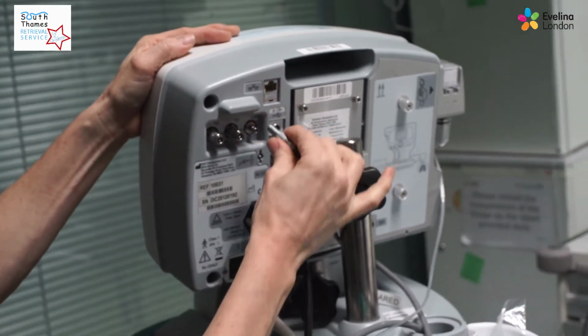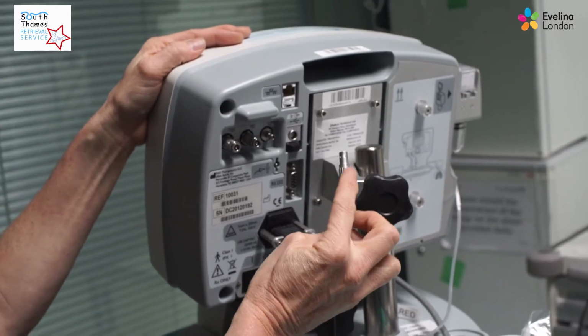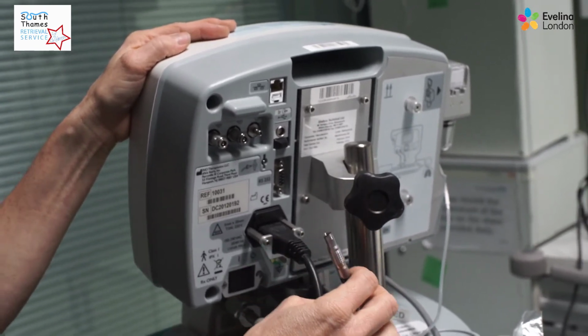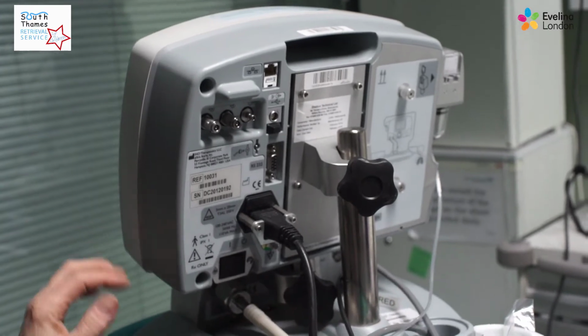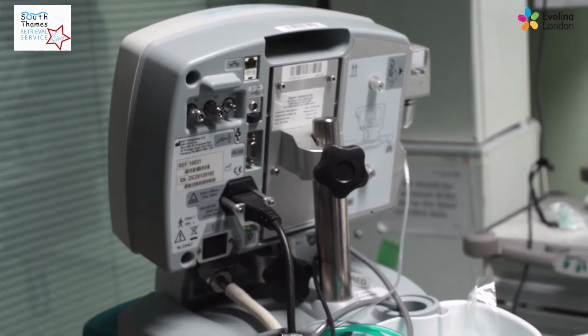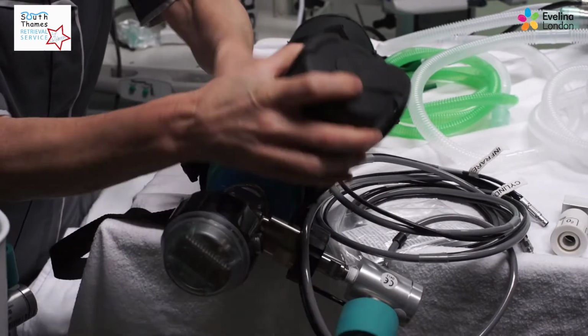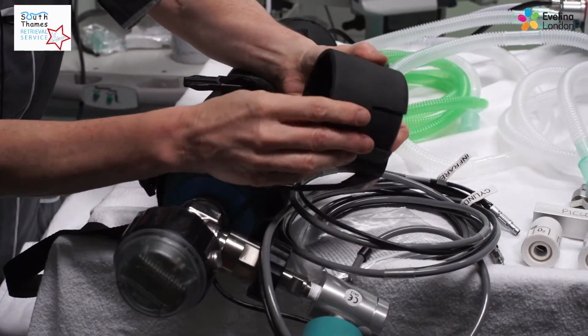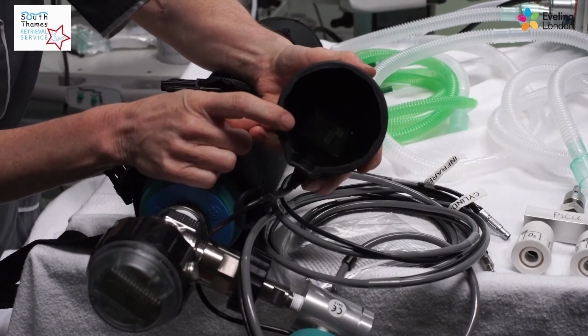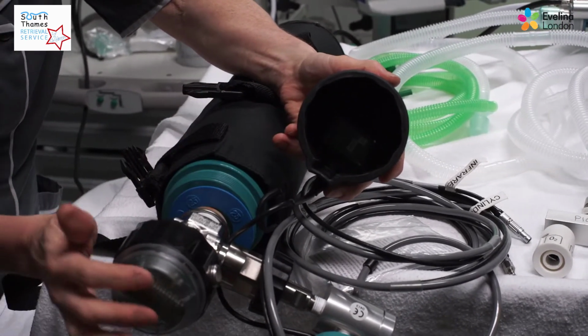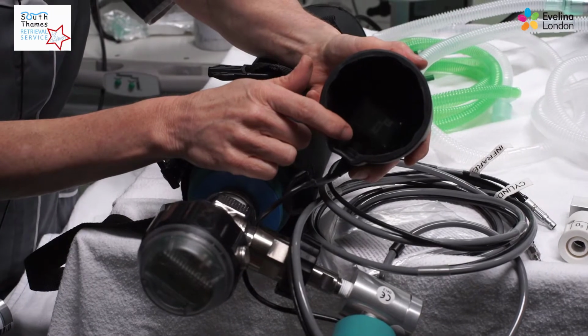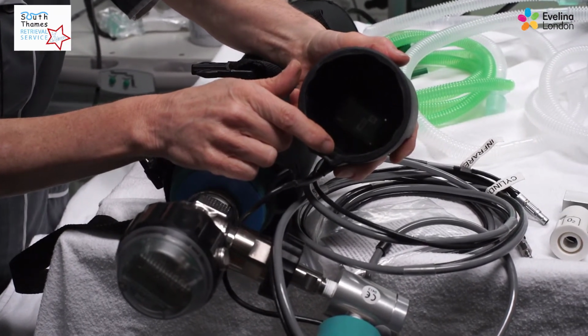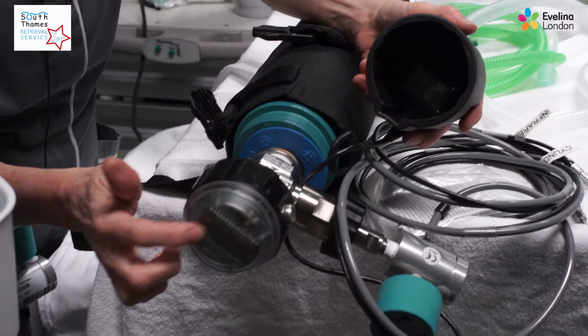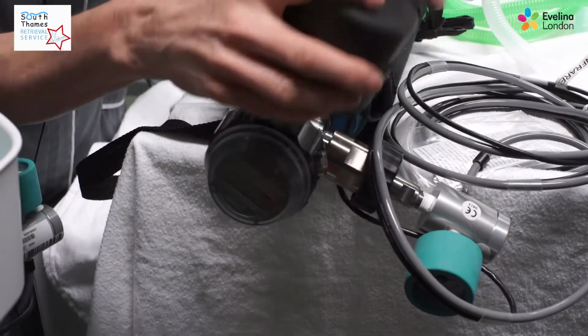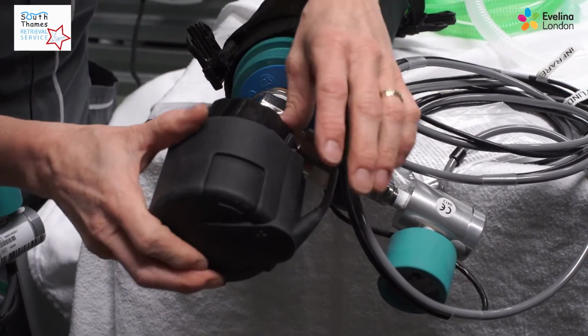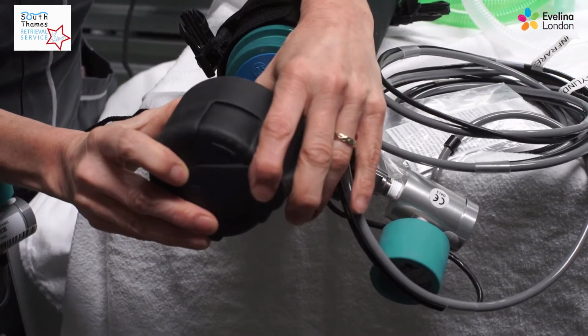And then you need to disconnect the last one, which is a black lead, an infrared lead, and it measures how much is being administered from the cylinders. If you go to the nitric portable system, this plastic cap has got a little infrared reading inside. So when the nitric is being administered, it monitors exactly how much we use, and we're charged per hour of use. And if you look here, you can see how much nitric is still left in the system. And that gets put on so that the little button slides in through the indent.